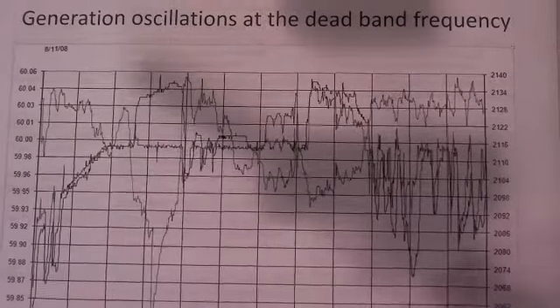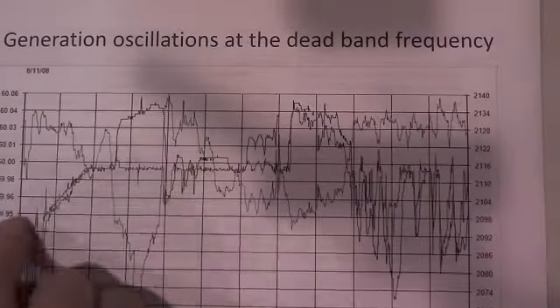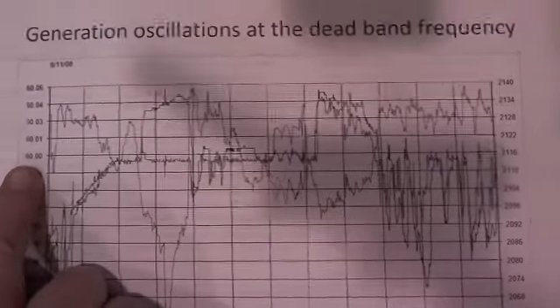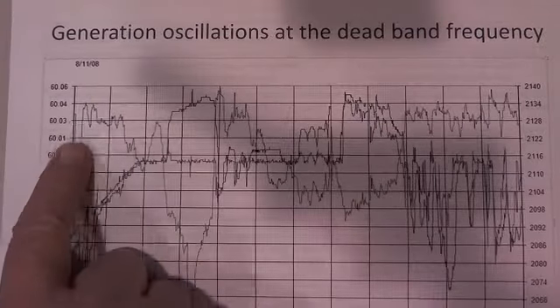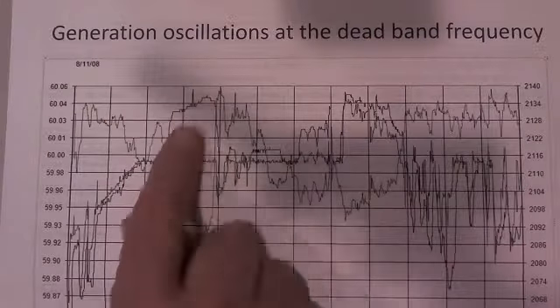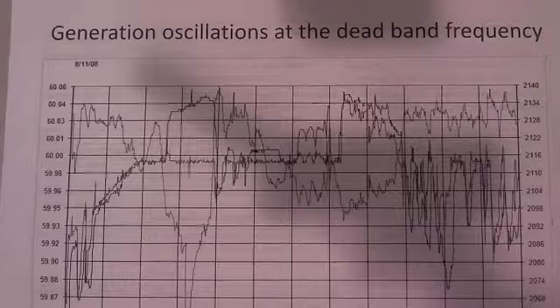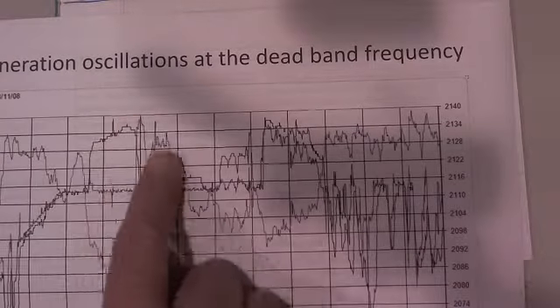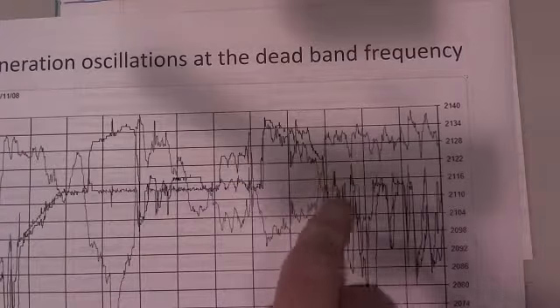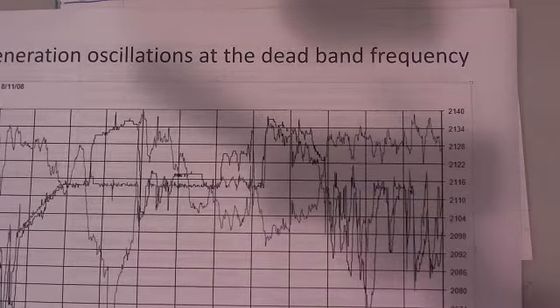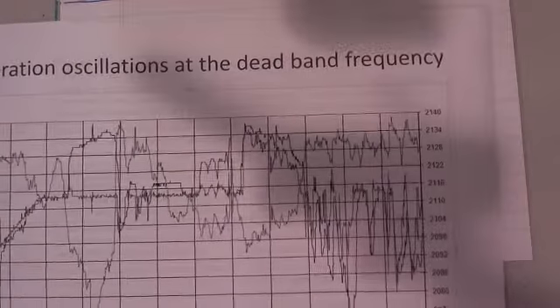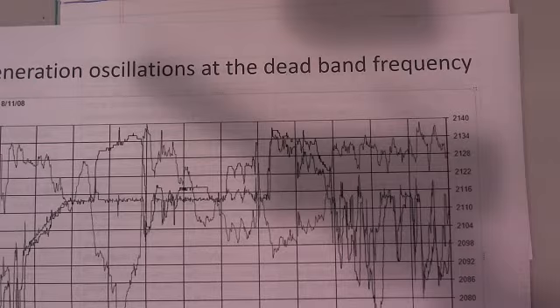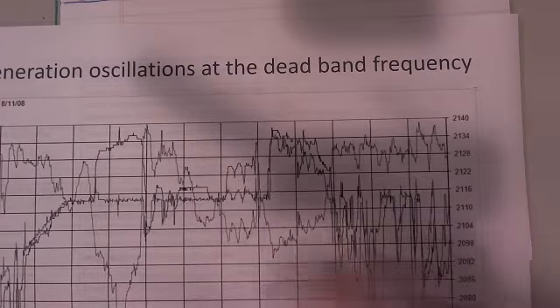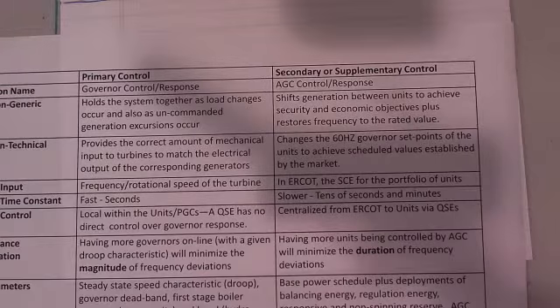in this slide. Here's, again without the color on here, frequency. Notice the scale here. Here's 60, right here where my finger is, going up at the most to 60.04 and down here to 59.8. And so you're seeing different oscillations and generators going up and down like this. You never get the frequency to be one absolutely still, flat thing, because load is always changing and going up and down. He's got a nice little summary at the end.